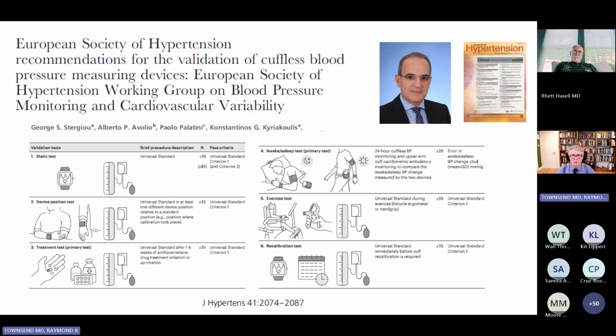But when the cuffless technology first blossomed, it really rocked the boat, because most of the things that we're checking for validation require a mercury cuff or the equivalent on one arm, and then the new device, called the investigational device, on the same arm, but you may have to shift cuffs. So you're doing a standard blood pressure measurement with 2 people listening, independent of one another. Hopefully their hearing is good. They're using a Y stethoscope. And then you interpose a device measurement. And then you do the 2 people and the device, and the 2 people and the device. And at the end of the day, you have 7 readings because it starts with the device and ends with the device, with 3 interspersed human readings.